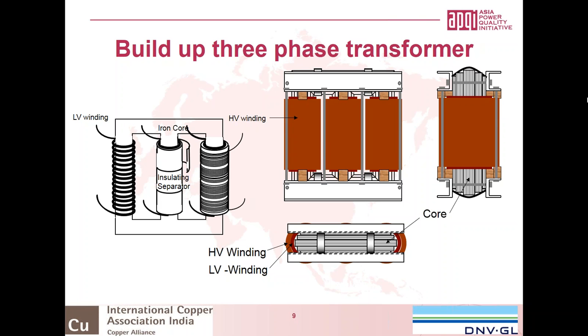If you look at the picture right next to it, you will also see on the outside, and this is just a dry type transformer which I've shown, that there are also some construction parts above the transformer to make sure that the windings are held firmly in place against each other because of failures within the transformer, short circuit failures. And if you look at the upper side, you will see that there is a yoke above the core, and also there you see some construction parts, and on the outside you will see a high voltage winding and a low voltage winding, which is around the core, one phase.